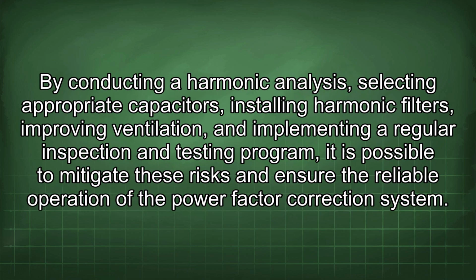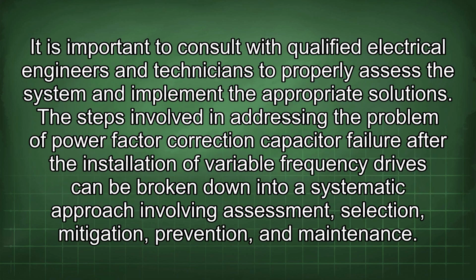By conducting a harmonic analysis, selecting appropriate capacitors, installing harmonic filters, improving ventilation, and implementing a regular inspection and testing program, it is possible to mitigate these risks and ensure the reliable operation of the power factor correction system. It is important to consult with qualified electrical engineers and technicians to properly assess the system and implement the appropriate solutions.